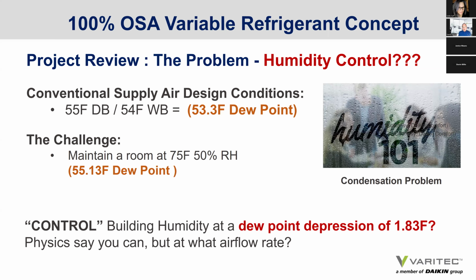In high performance buildings, we're tightening up our perimeter walls. We're using better insulation. We're using improved glazing to reduce the radiant load through windows. Our sensible loads are going down, but our humidity loads are not going down. So as we reduce air flows because of our good design practices architecturally, and we're not adjusting for the humidity, we're going to run into a humidity issue, which results in mold in buildings and other consequent effects we don't want to see. So this is a question that needs to be brought to the foreground, especially as the AIA is trying to meet their 2030 commitment and decarbonizing buildings through more efficient design strategies. Is 1.8 degree dew point depression adequate?